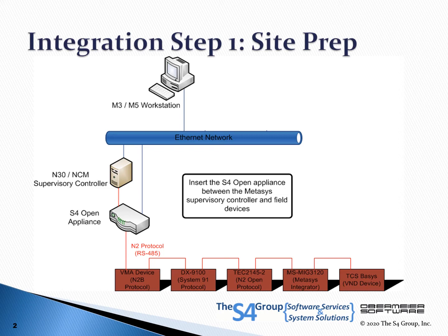A best practice is to run a HVAC Pro devices report to document your baseline condition. Reprogram, recommission, repair, or replace N2 devices as required. Then, insert the S4 router into the configuration, connecting the N2 bus to the downstream N2 interface and the Metasys supervisor controller, if coexistence is licensed, to the upstream N2 interface.